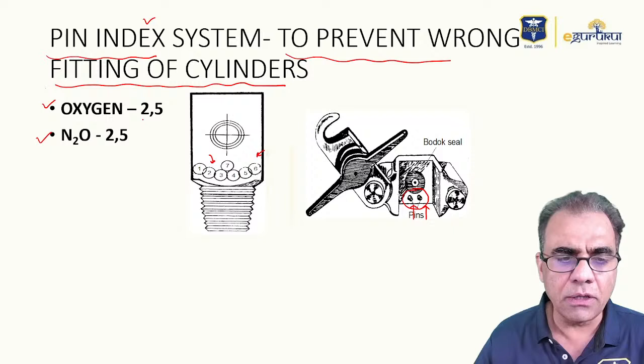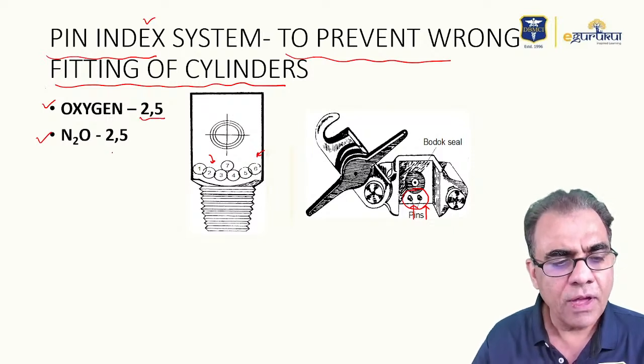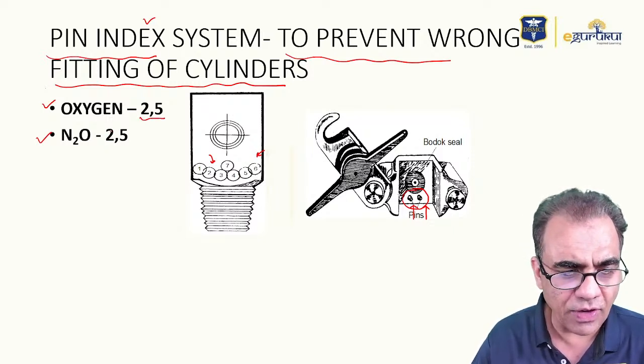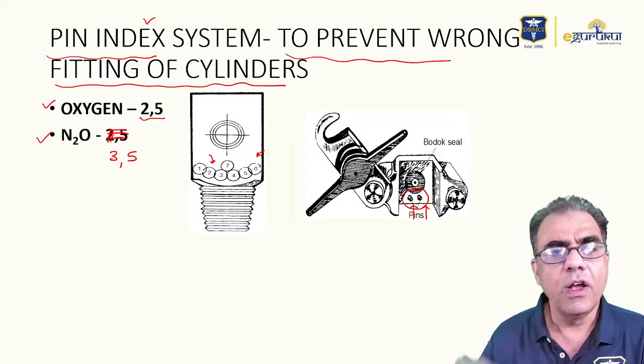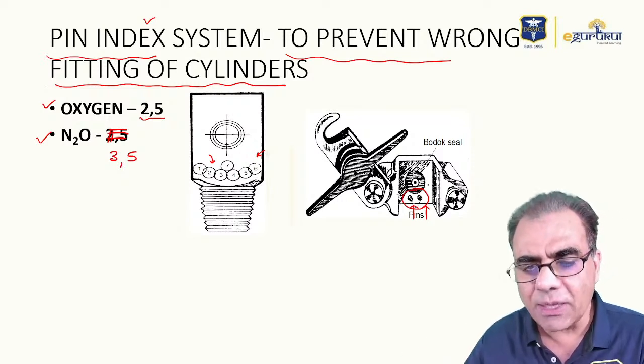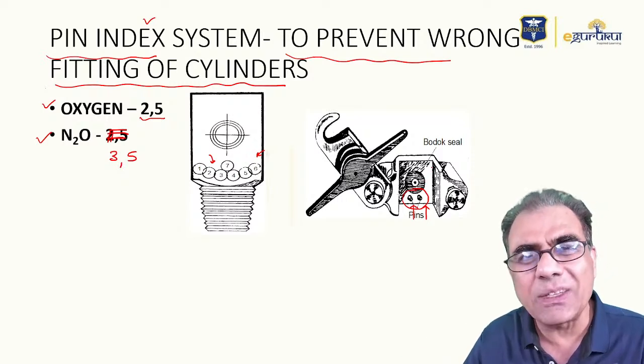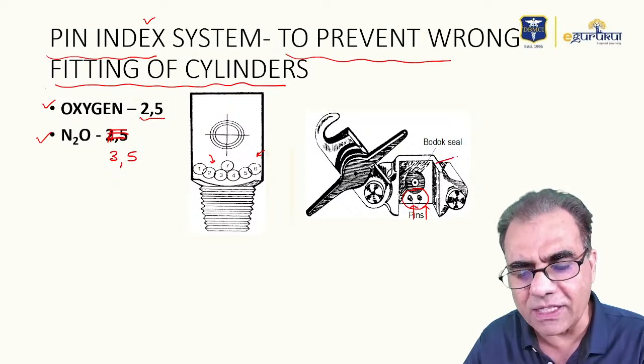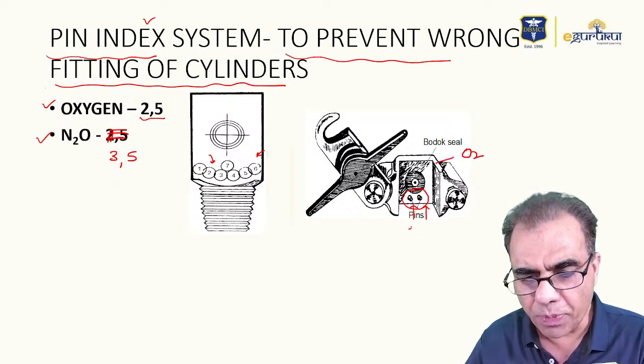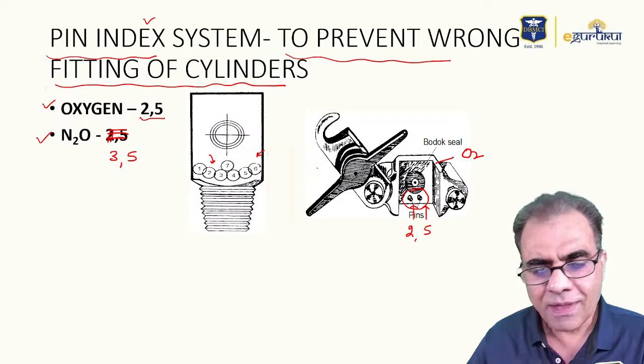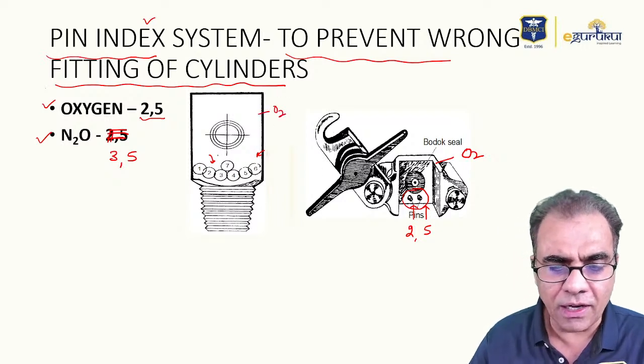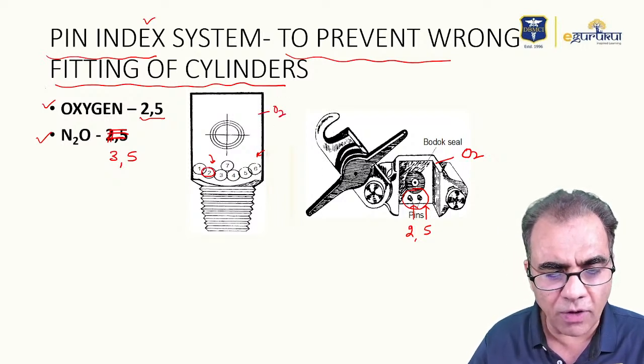The pin index position for oxygen is 2 and 5, while that of nitrous oxide is 3 and 5. You can correct it: it is 3 and 5 for nitrous oxide. What does that mean? This is the place where, for example, the oxygen cylinder will be fitted on the anesthesia machine. The pin positions will be 2 and 5, and if this is an oxygen cylinder, the hole positions will be 2 and 5.